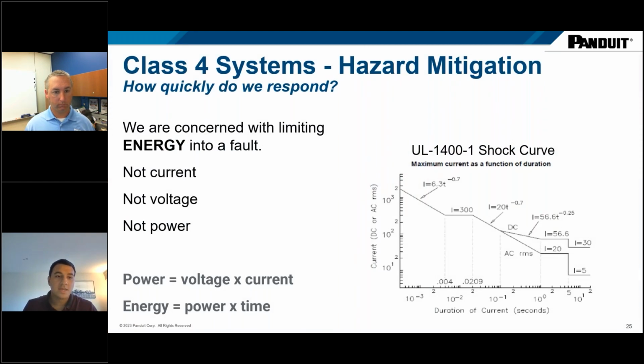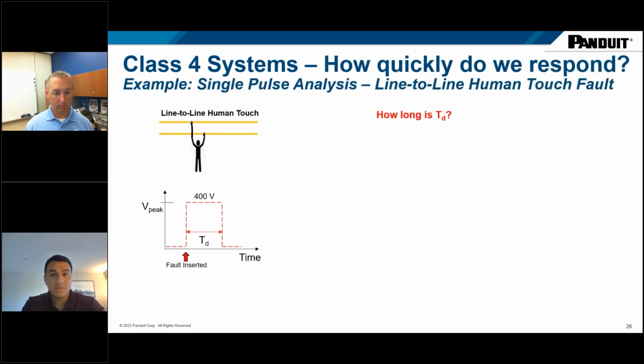So the first thing I want to highlight is, again, we are concerned with limiting energy going into a fault. We're not limiting current or voltage or power, we're limiting energy, which is power over time. And UL has defined shock as how much current flows through the heart. The limits that you see in the graph here are basically the limits that they came up with, and these are specified in the standard. So we're going to use this graph to see how we can design a system. Think with me, this is just a very simple example.